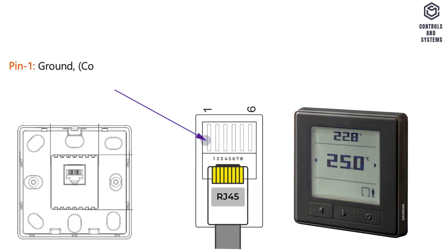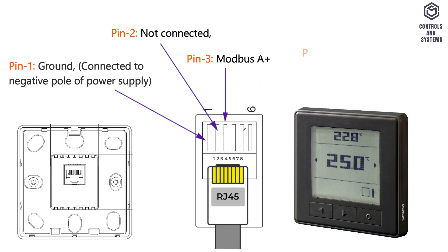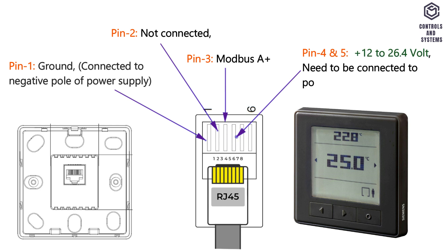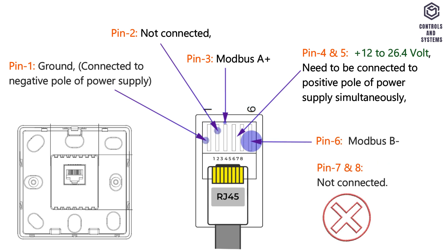Pin 1 is ground, connected to the negative pole of the power supply. Pin 2 is not connected. Pin 3 is Modbus A+. Pin 4 and 5 is +12 to 26.4 volt, and pin 4 and 5 need to be connected to the positive pole of the power supply simultaneously. Pin 6 is Modbus B-, pin 7 and 8 are not connected.